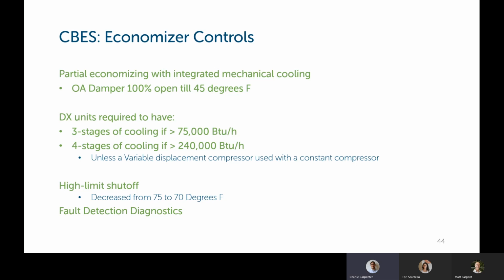The high limit temperature shutoff for an economizer has been decreased from 75 degrees down to 70 degrees Fahrenheit. So that'll increase the range that you could use them throughout the year. And the economizers also need to have fault detection diagnostic controls. Next slide.